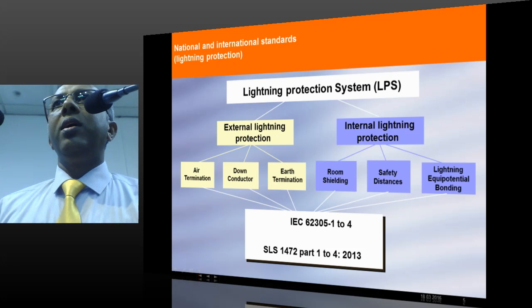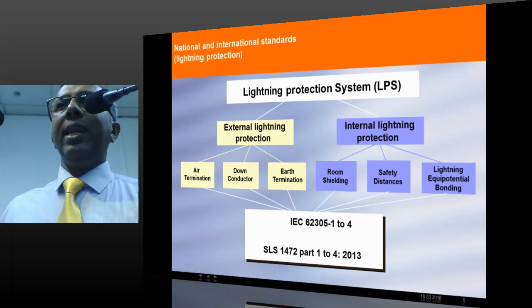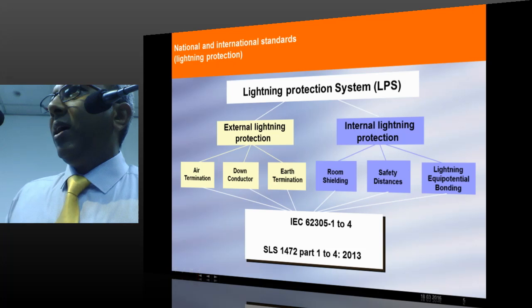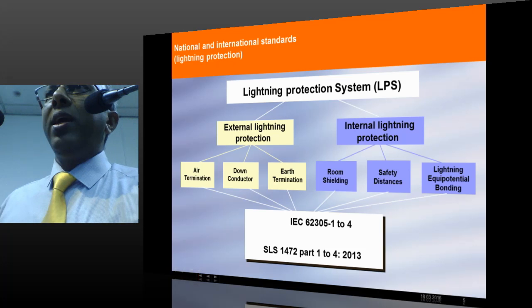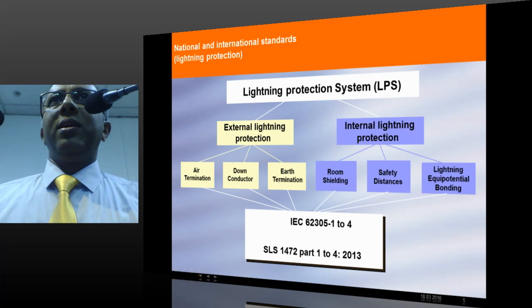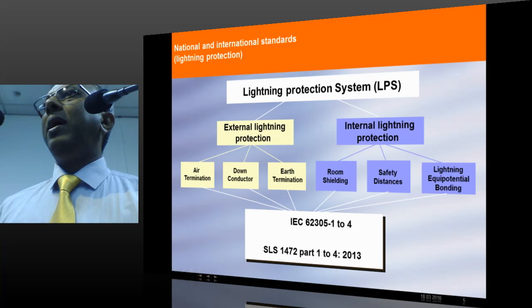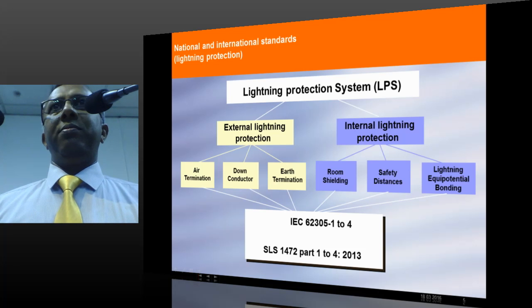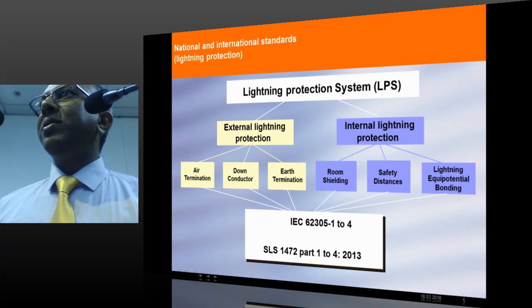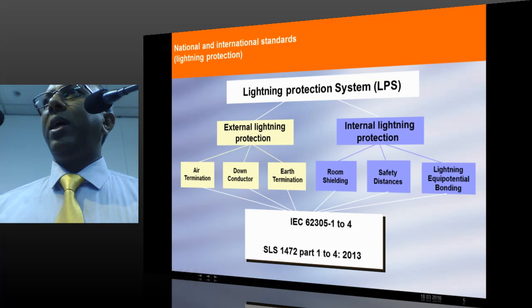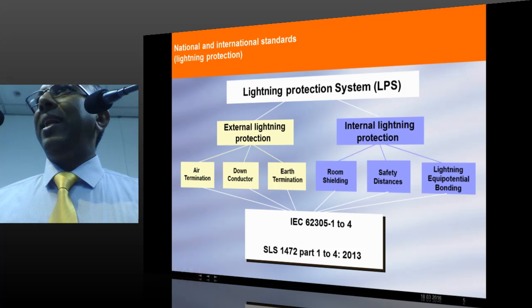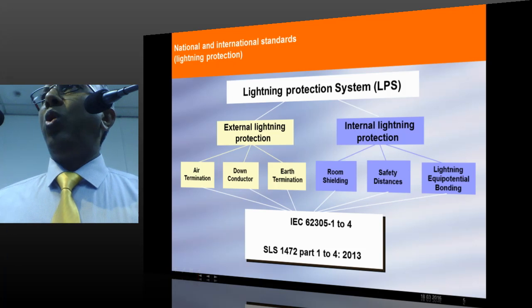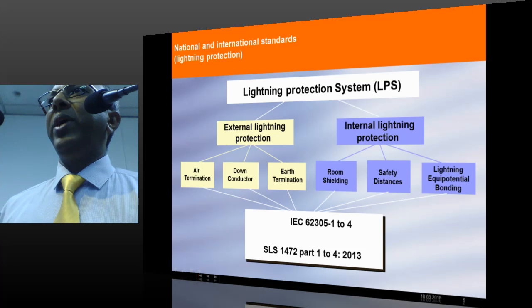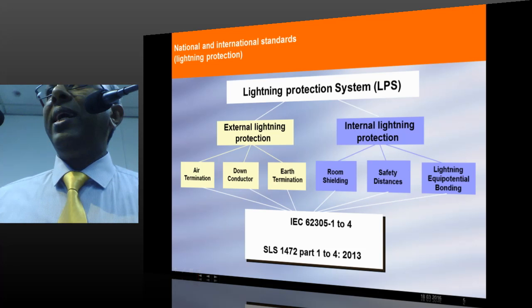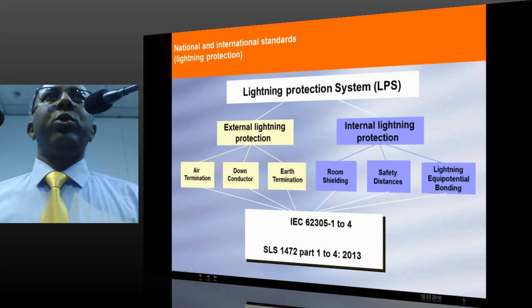So, the 3 subjects, room shielding, safety distances and lightning equipotential bonding is important. What we talk about lightning equipotential bonding is, during a transient condition, all metallic parts in a building have to be brought to the same potential. All metallic parts in a building means, number one, lightning protection system, air termination, down conductor, earthing, reinforcement of steel in a building, metallic windows, doors and so on, the phase and neutral of a power supply line, copper conductors of a communication or a telephone line. So all these metallic installations need to be brought to the same potential so that there is no potential difference.